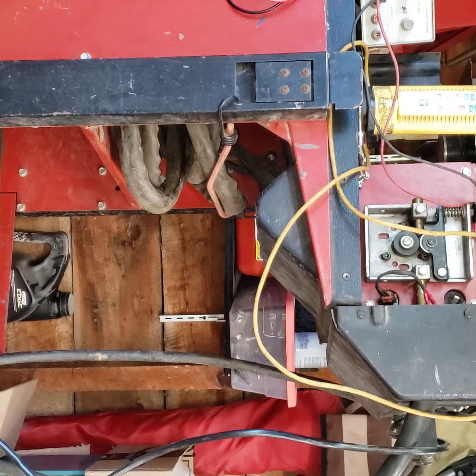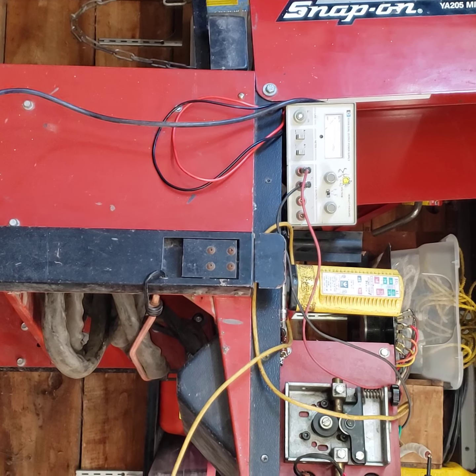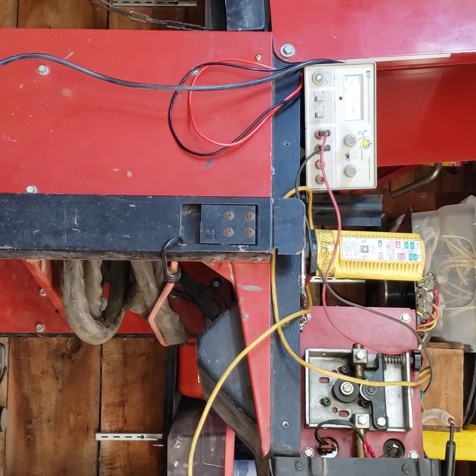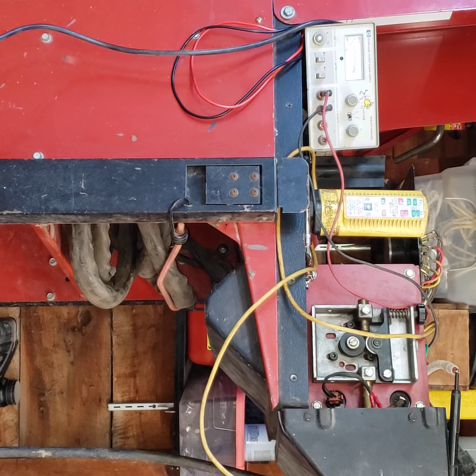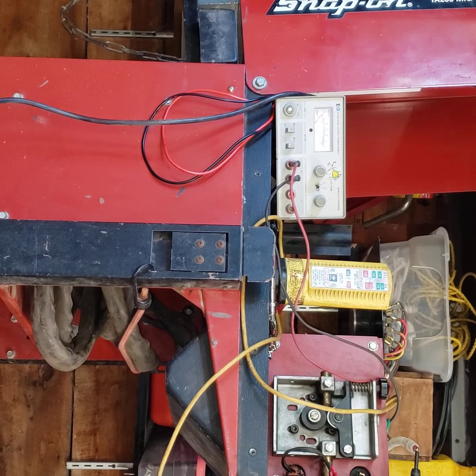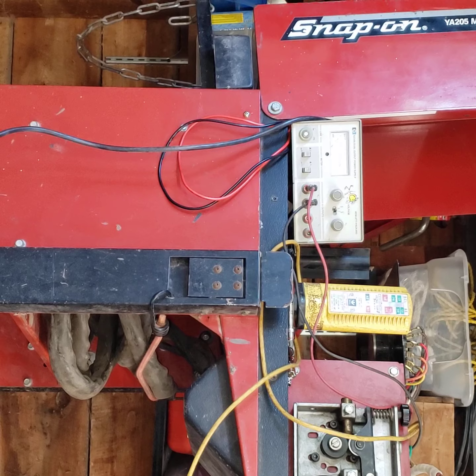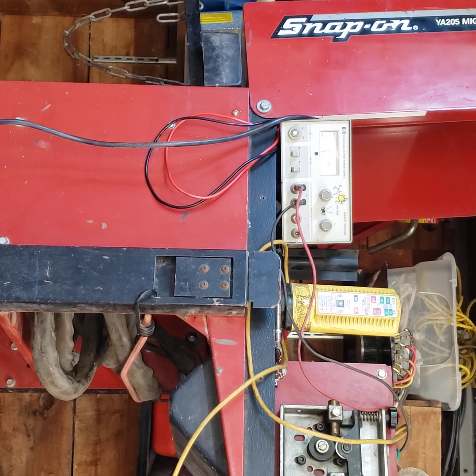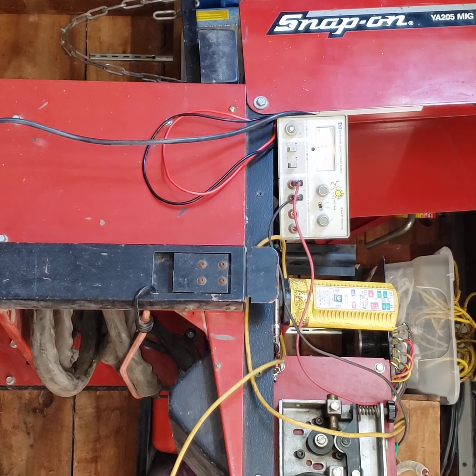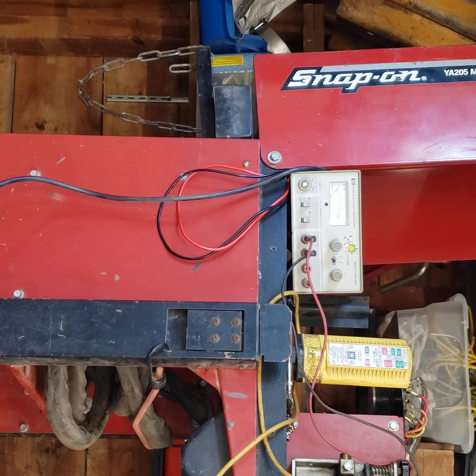So let's say I plug the test lead in — this is going to power the meter. Right now I have nothing. When I plug in the power supply, you'll probably see the needle moving. We shouldn't see the Wiggy moving yet. Maybe you'll hear it. And hopefully you can hear the Wiggy moving — so that means this SSR, this solid-state relay, is good.